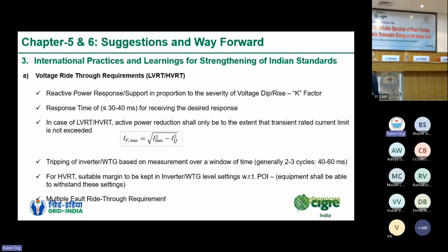Like voltage ride-through requirements, our requirements are also comprehensive, but to elaborate them further, certain points can be adopted, like reactive support based on the severity of voltage dip. There can be a mention of response time for receiving the desired response. In case of LVRT and HVRT, in our standards it is written that reactive power will be given first priority, but what shall be the limit of active power reduction, and the extent to which plants can reduce, is not exactly specified. So mentioning them could help in the standards.